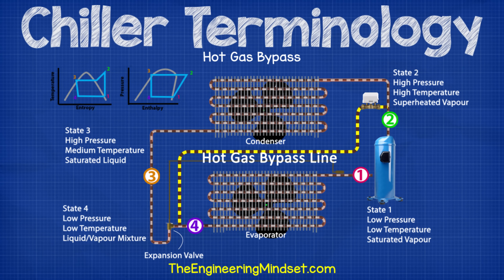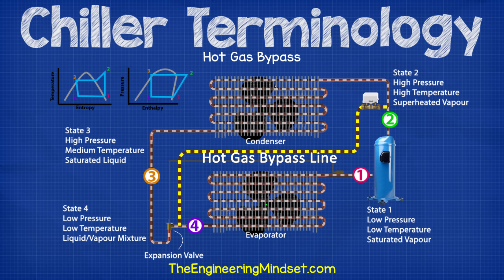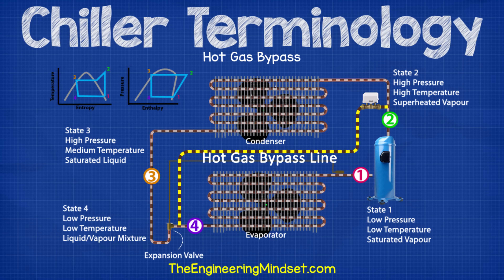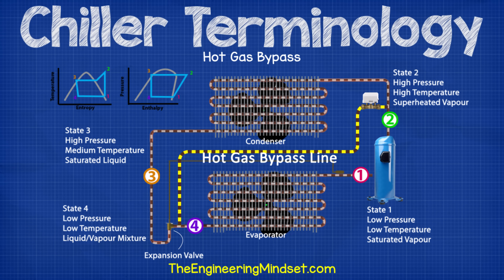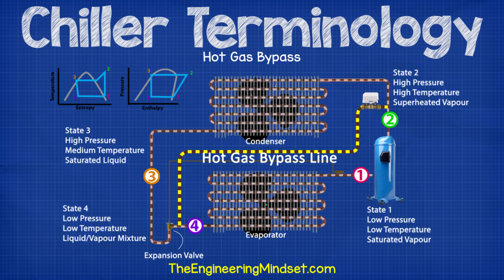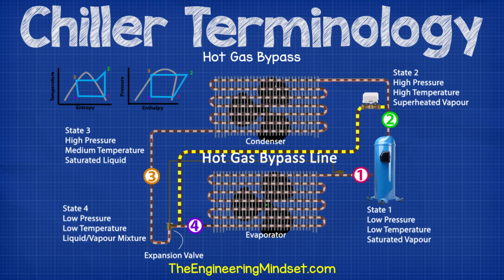Hot gas bypass. This is only used on some chillers. It is used to create an artificial cooling load to stop the chiller from cycling, stalling, or surging, as well as protecting the evaporator from freezing under low load conditions. A control valve is used along with a pressure-reducing valve to recirculate hot refrigerant from the compressor discharge line and send it straight to the inlet of the evaporator, bypassing the condenser so that heat is added to create a false load. This is a pretty inefficient strategy — the energy that went into the compression of the refrigerant will provide no usable cooling effect. If you're using this strategy, then your chiller is likely way oversized.